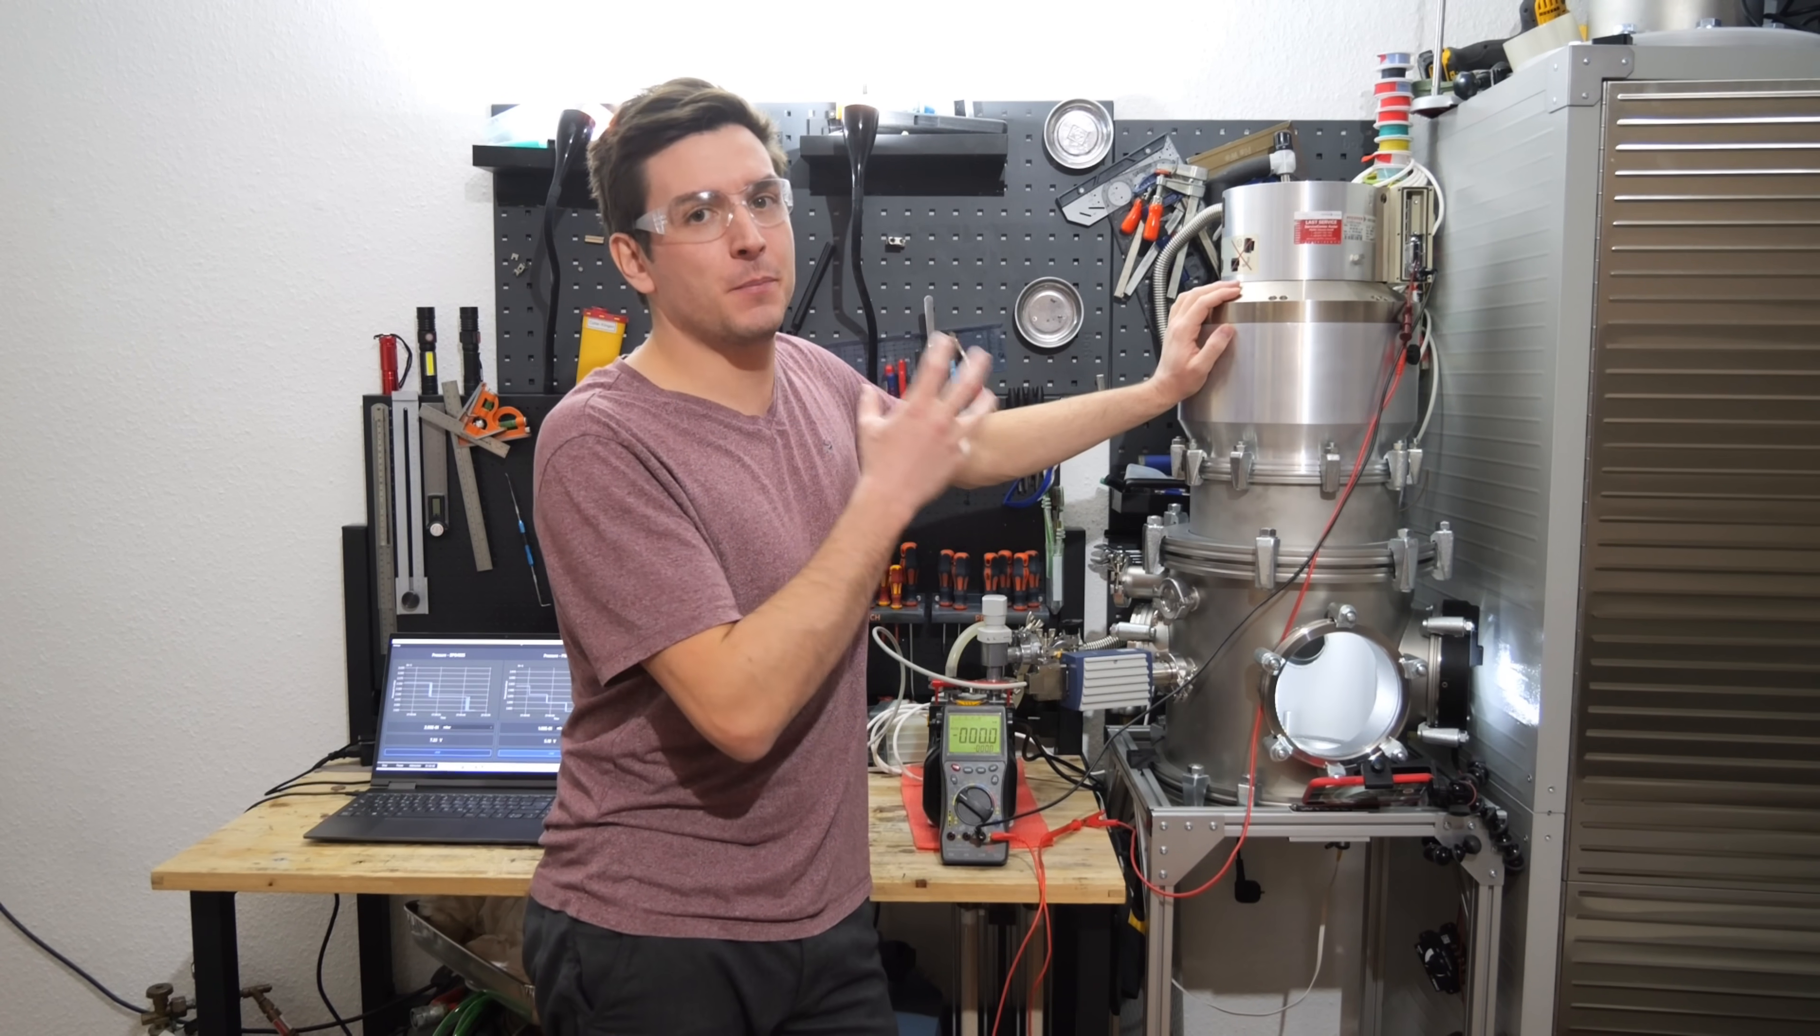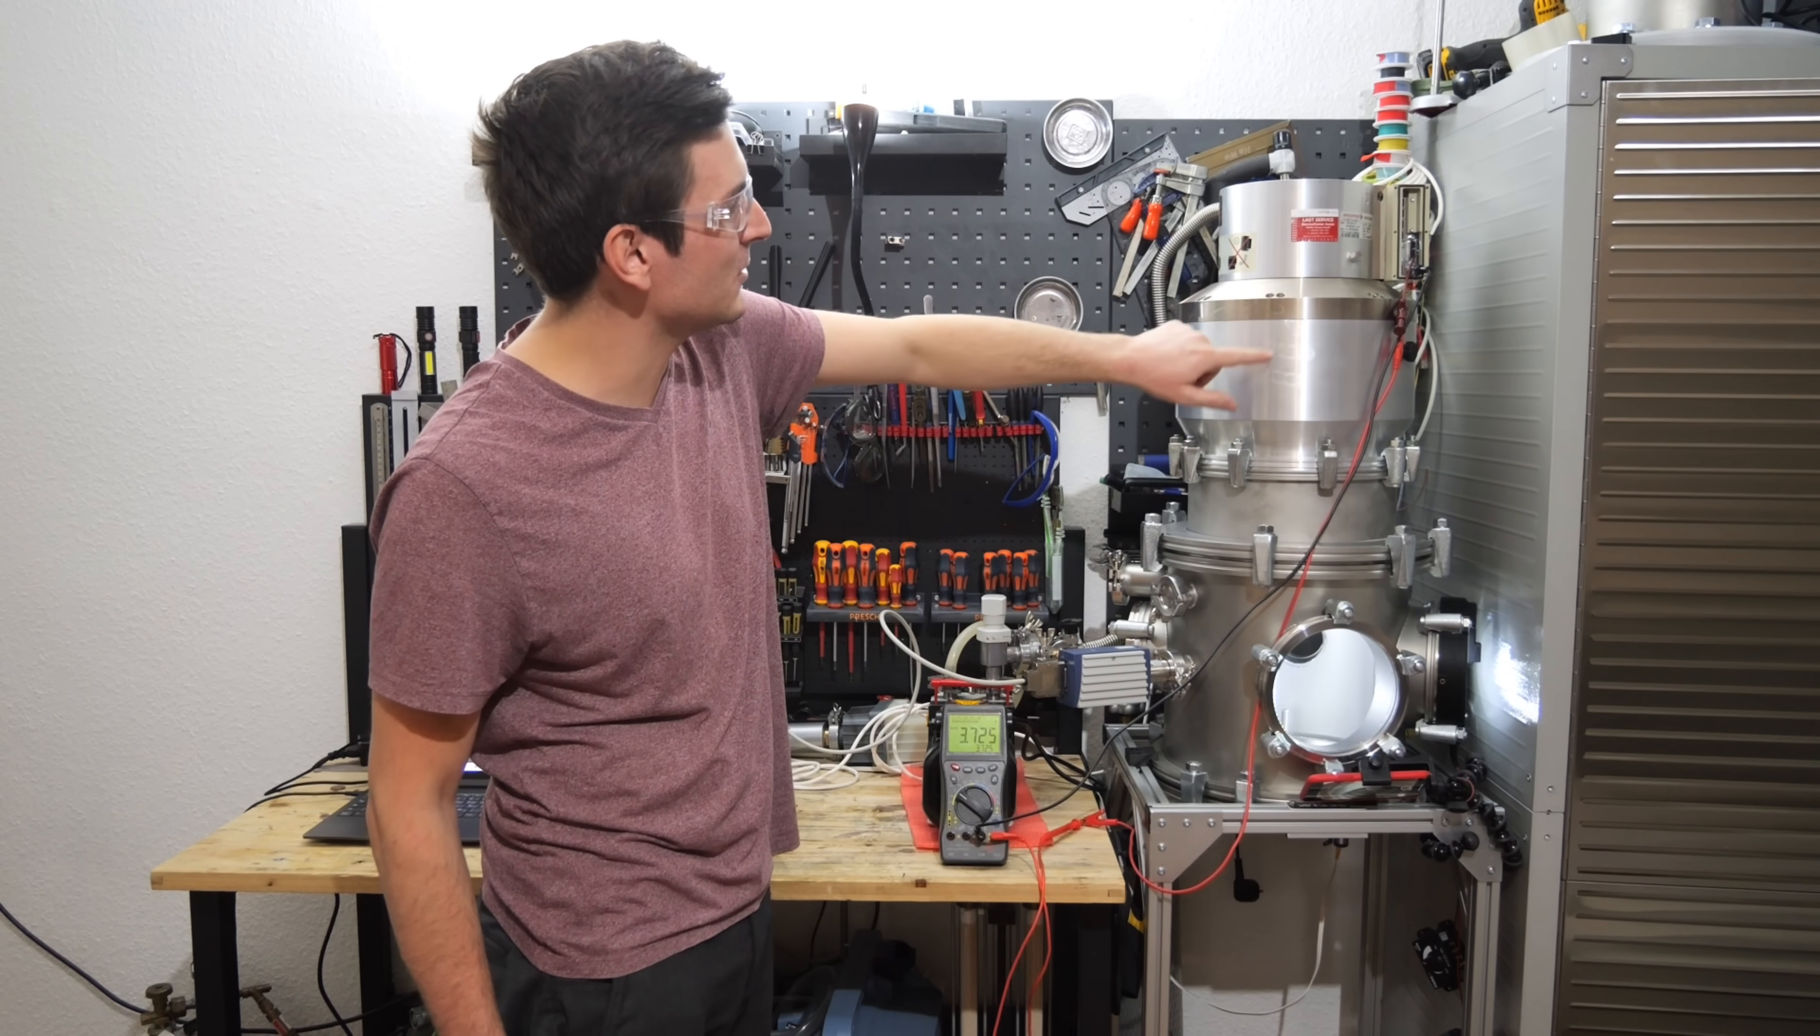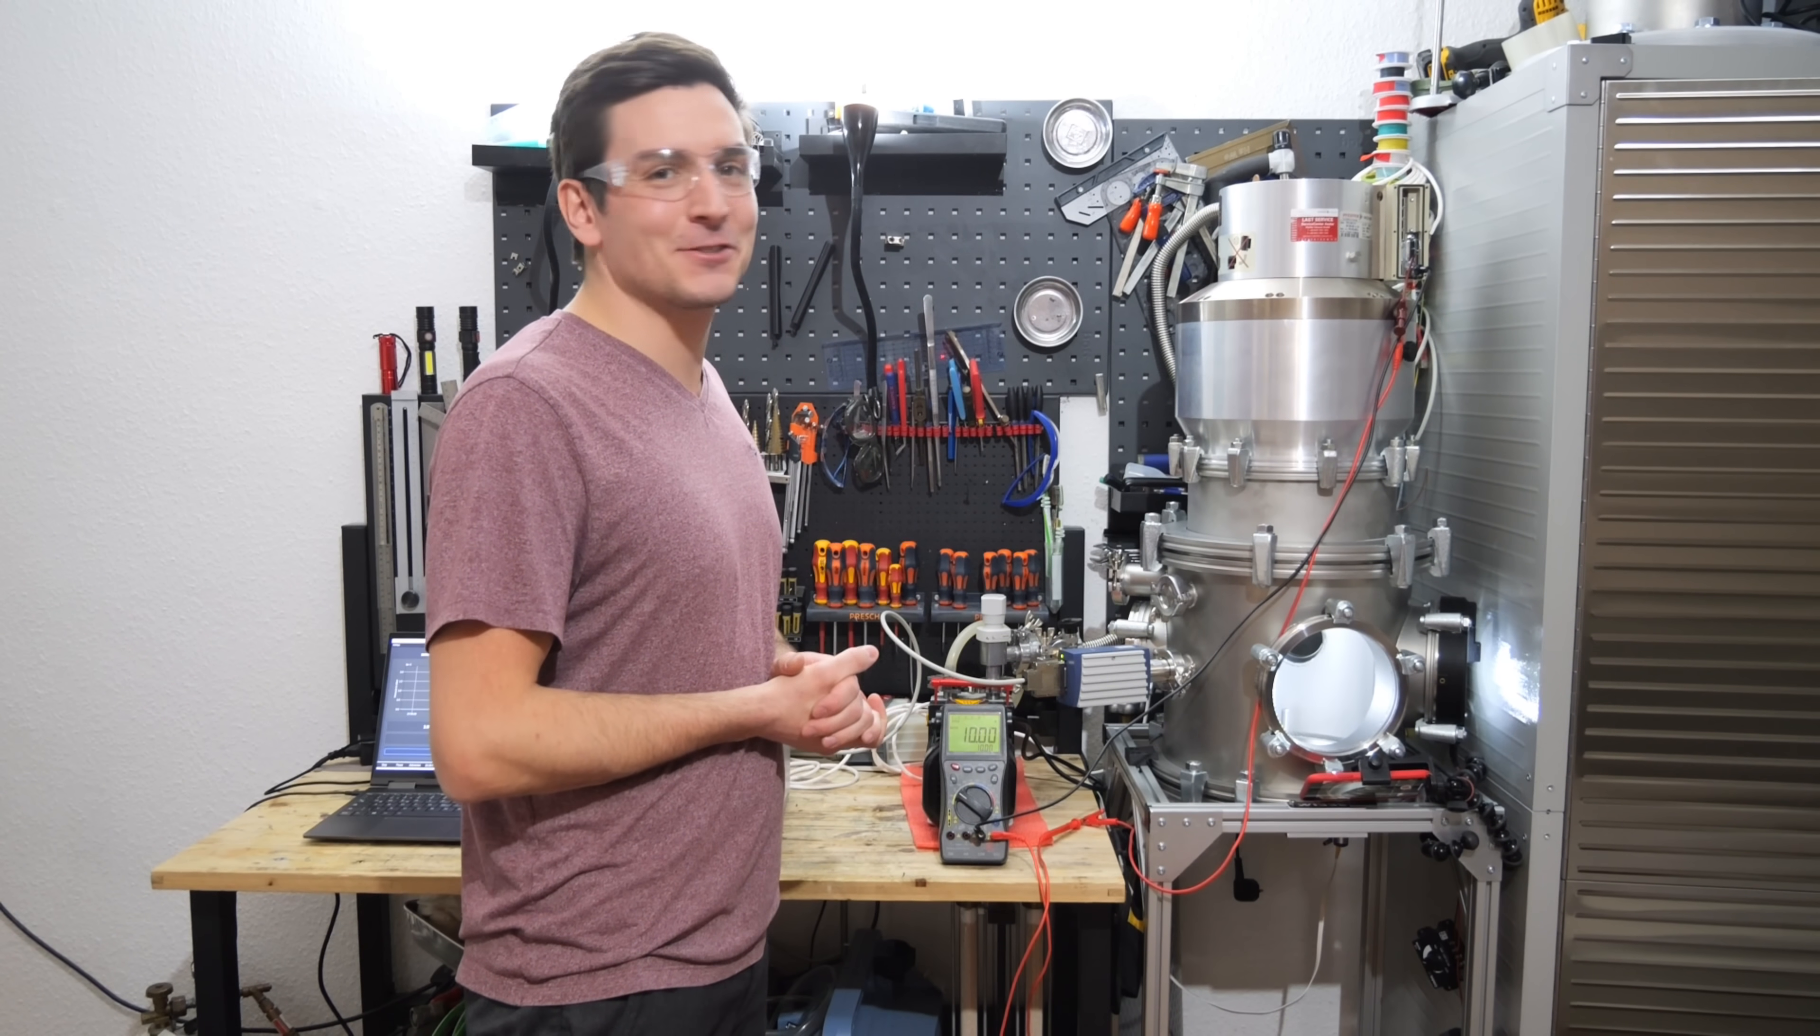Now that I know that the pump I didn't mess with makes the same noises at around 10% speed, I'm trying to restore my honor and that's why I reinstalled the pump I disassembled and reassembled again. You can see how stressed I am by my sweat on the pump here. Everything looks good. The pump is running fine, so I'm very relieved that I didn't mess it up when working on it. We are currently at a pressure of 4 times 10 to the power of minus 6 millibars and yeah, looks great, we are at 100% speed. I'm very satisfied.